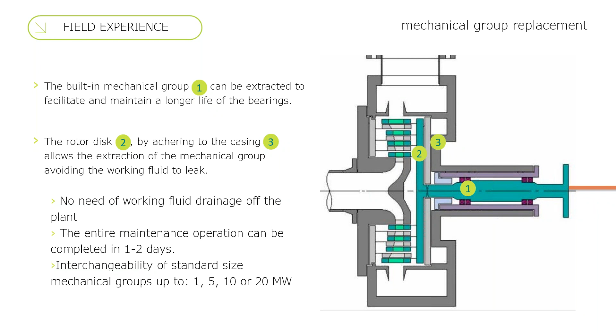And with a focus on the radial outflow turbine, which is a patented technology and finds the largest number of applications right in the geothermal binary cycles field. In this case, this turbine is designed to have the wear parts, the bearings and the mechanical seal, in this kind of cartridge, which is the mechanical group, and this holds the rotor. And by moving the rotor toward the turbine case, the plant is sealed, so there is no need of draining the fluid of the plant and refilling it at the end of this operation, with a lot of time saving in terms of maintenance. And this mechanical group cartridge can be extracted, and the new one can be put back in, with the whole operation completed in between 1 and 2 days.